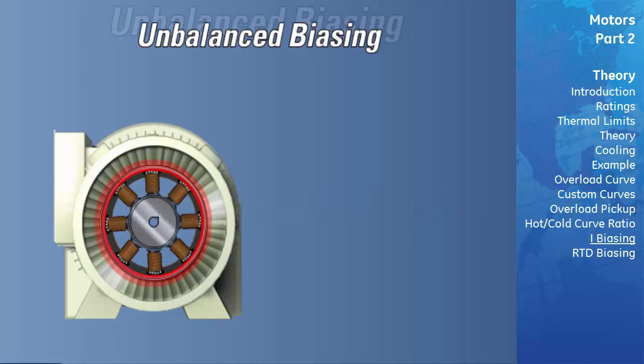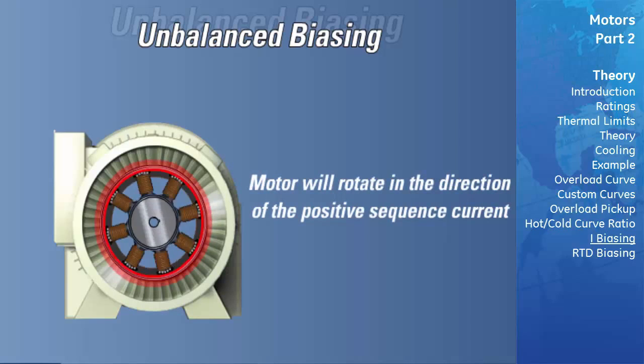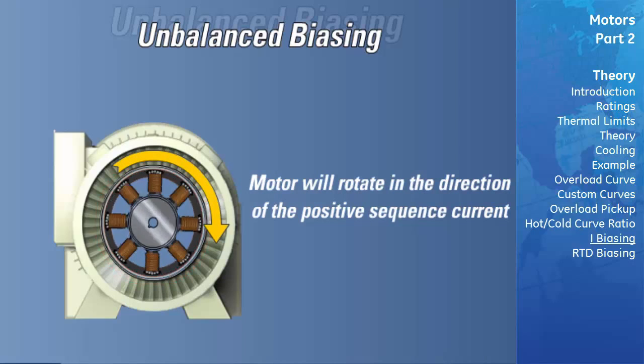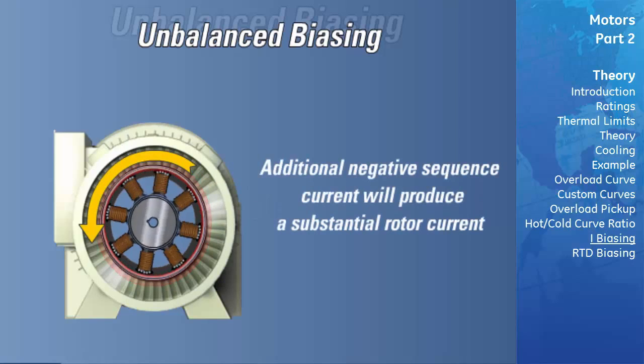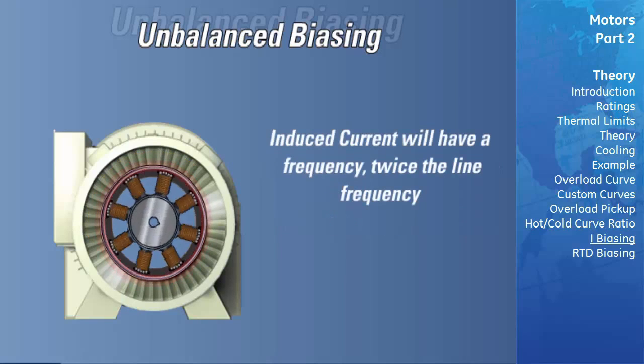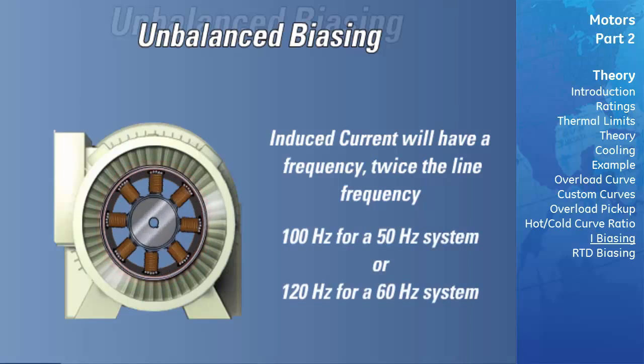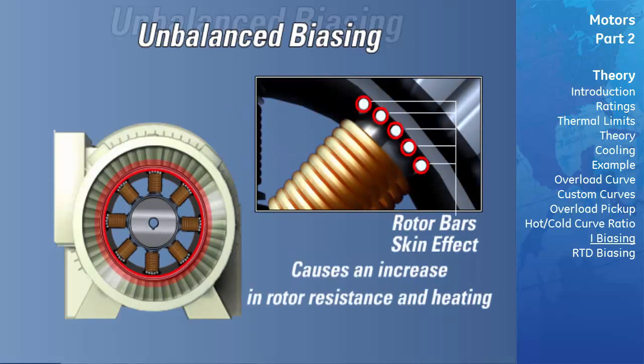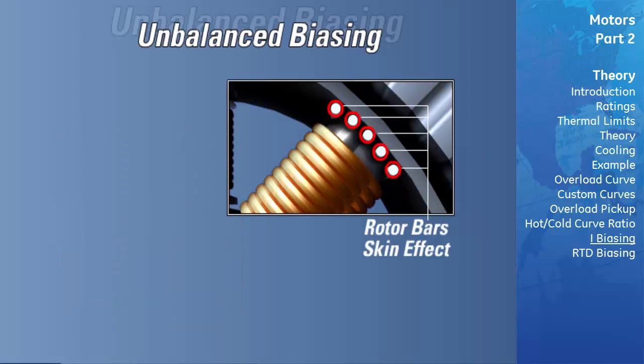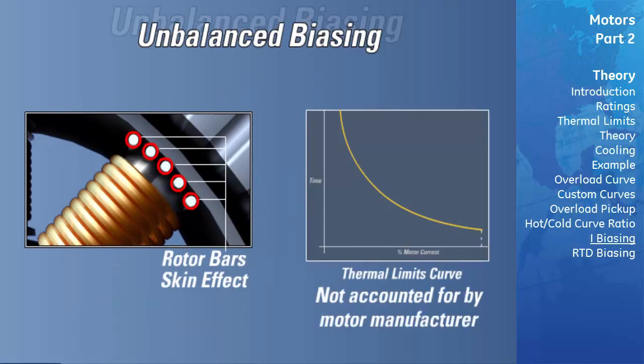When the motor is running, the rotor will rotate in the direction of the positive sequence current at near-synchronous speed. Negative sequence current, which has a phase rotation opposite to the positive sequence current and hence opposite to the rotor rotation, will generate a rotor voltage that produces substantial rotor current. This induced current will have a frequency approximately two times the line frequency — 100 Hz for a 50 Hz system, or 120 Hz for a 60 Hz system. Skin effect in the rotor bars at this frequency will cause a significant increase in rotor resistance and therefore a significant increase in rotor heating. This extra heating is not accounted for in the thermal limit curves supplied by the motor manufacturer, as these curves assume positive sequence currents only from a perfectly balanced supply.